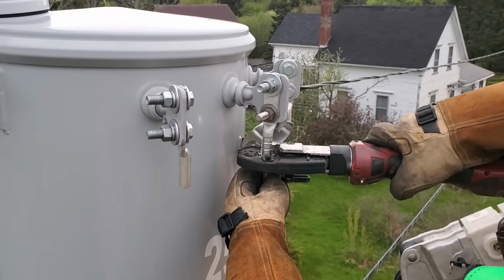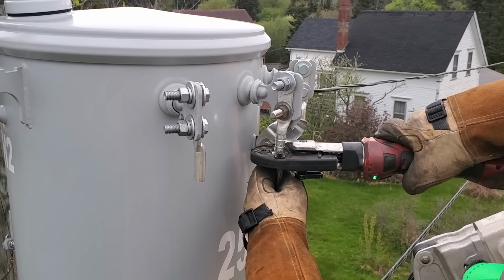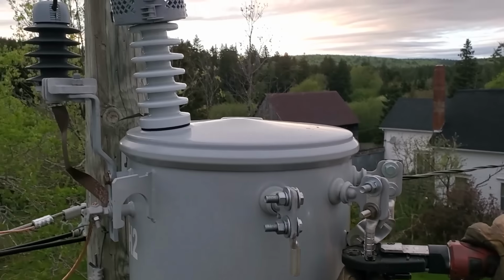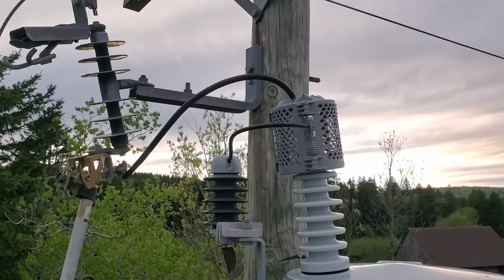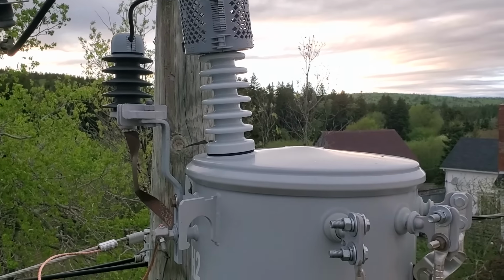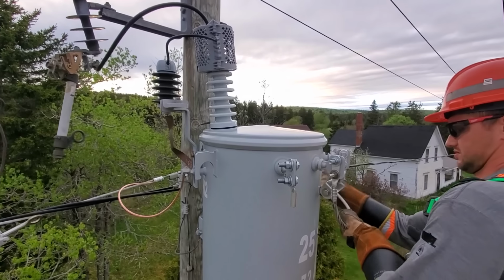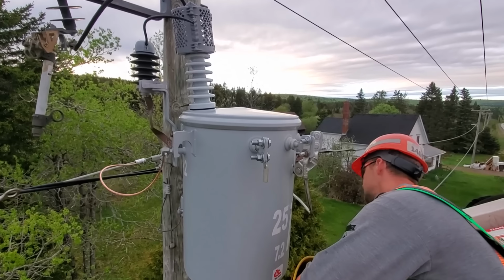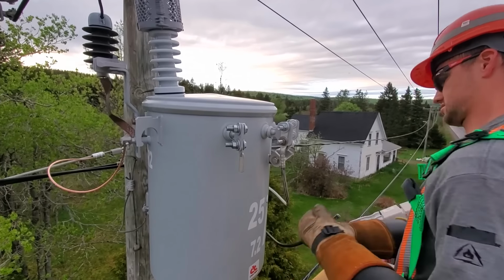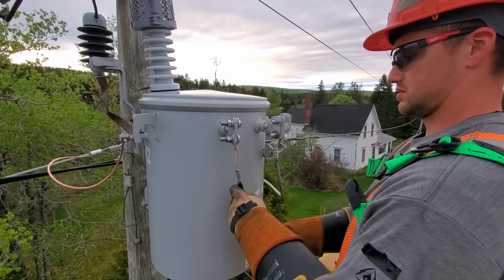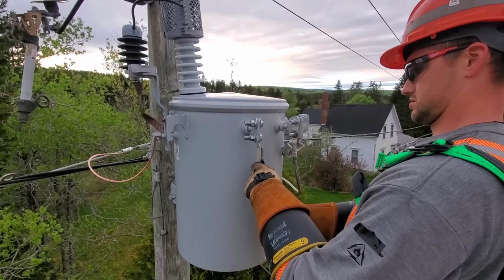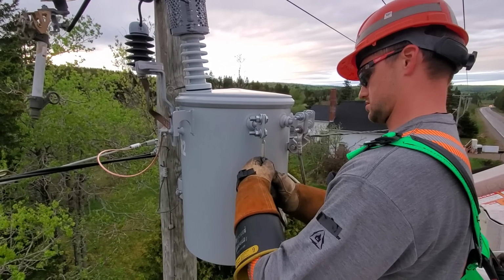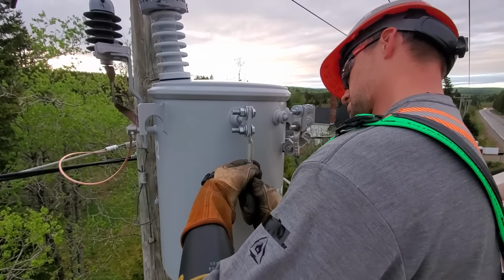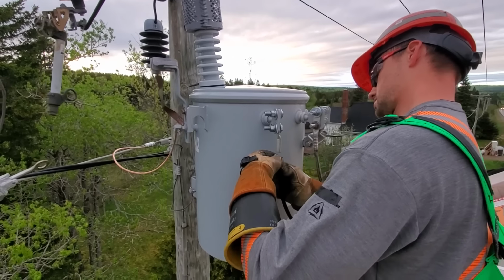So at this point where he's hooking up the secondary lead, he can absolutely not go onto any of the primary connections on this transformer where there is potential for backfeed. If he did forget something and had to go back onto the primary, at this point he'd have to either remove these secondary leads or install secondary grounds, which we've seen in a few past videos. Basically jumper cables just short out from each of the hots to the neutral in the center.